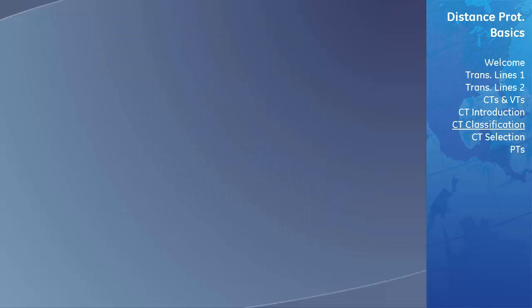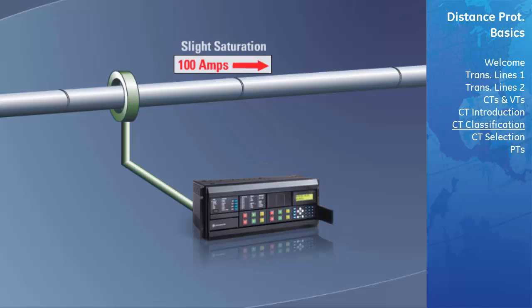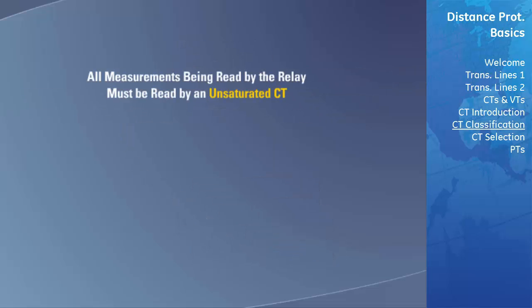To demonstrate how a relay measures a saturated CT: if 100 amps are passed through the CT primary under no saturation, then 100 amps is read by the relay. If those 100 amps cause slight saturation, the relay's measurement decreases and instead reads only 50 amps. If the 100 amps cause severe saturation, the relay reads only 25 amps. The greater the saturation, the more inaccurate the measurements will be. It is imperative that all measurements read by the relay are from an unsaturated CT, so appropriate CT selection must be made to ensure the rated CT can handle the applied current without saturating.